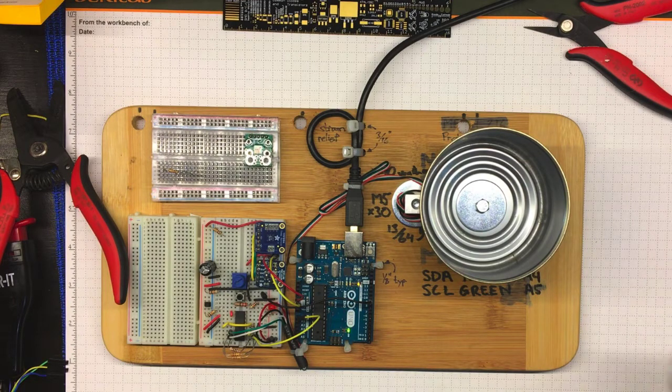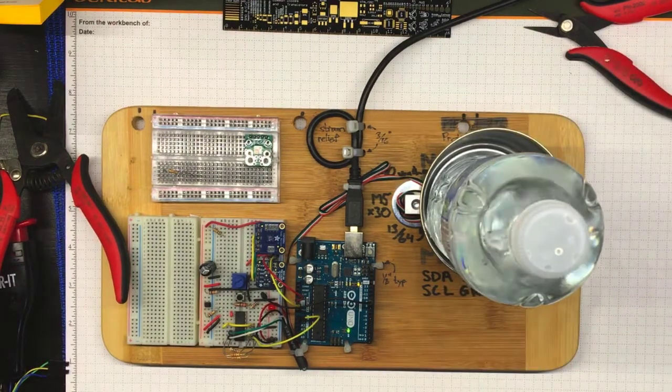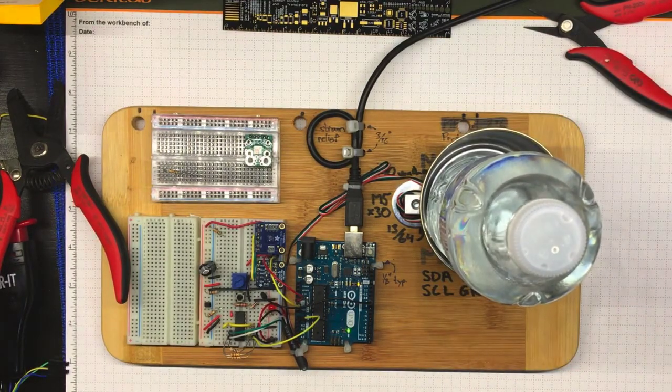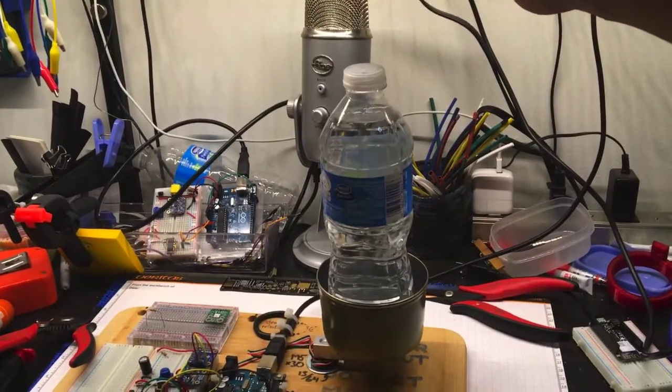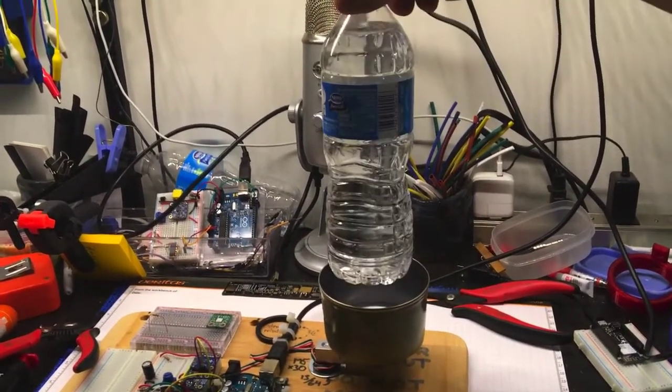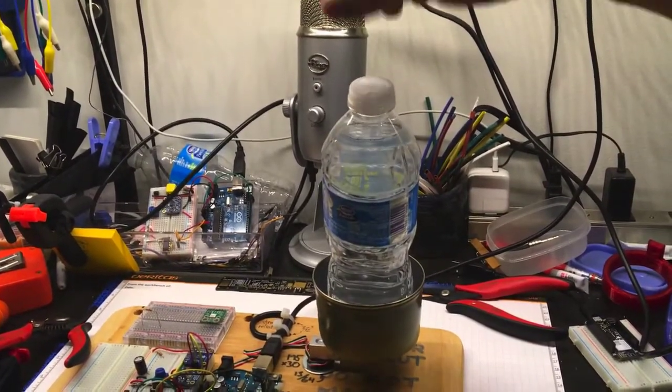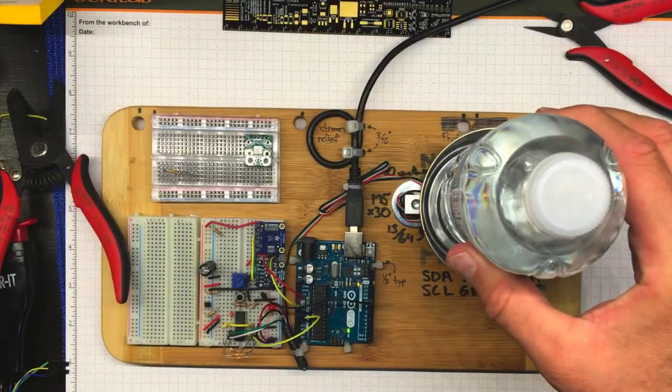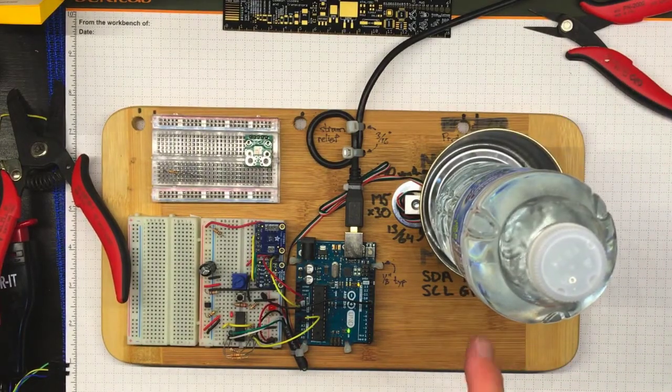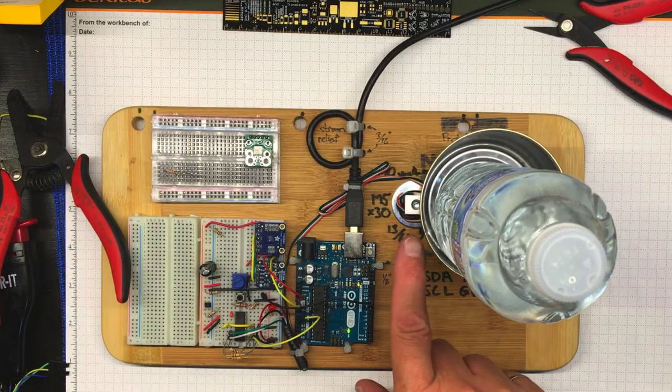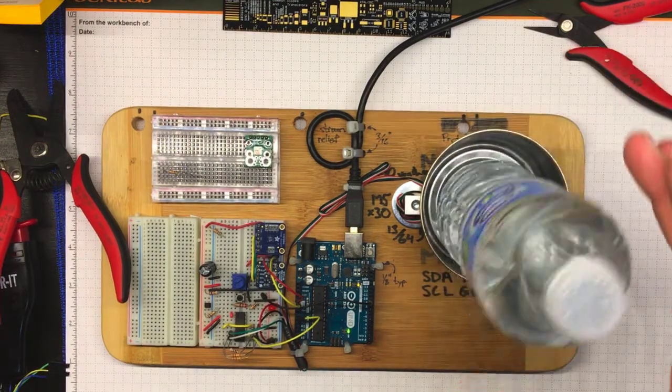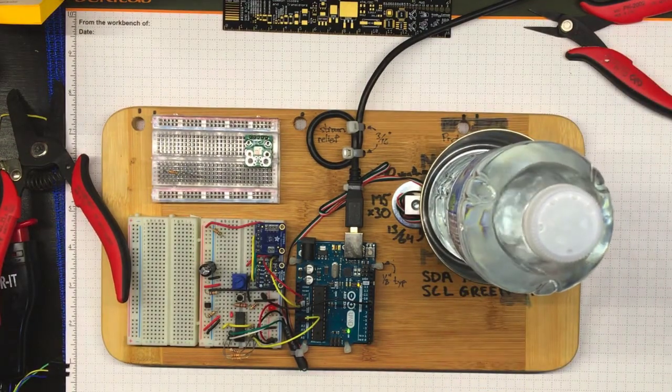Now let's have a look at what happens. If I take the water bottle and drop it in, it bounces. But it doesn't bounce up and down nearly as long and nearly as far as it did with that cantilever beam load cell that was really quite springy. Let's watch that again. Drop it in. It's actually the bottle that's bouncing, not so much the load cell. The bottle itself is flexible.